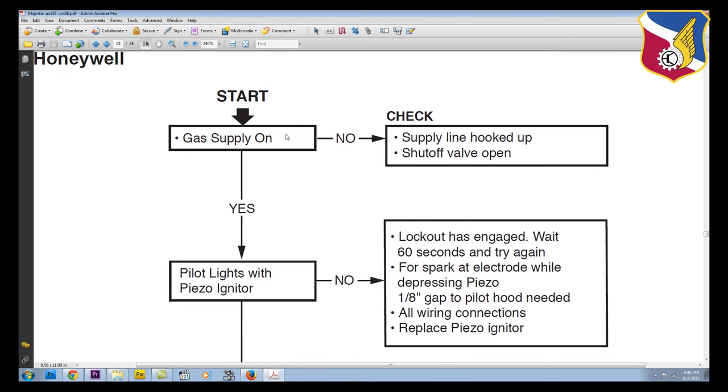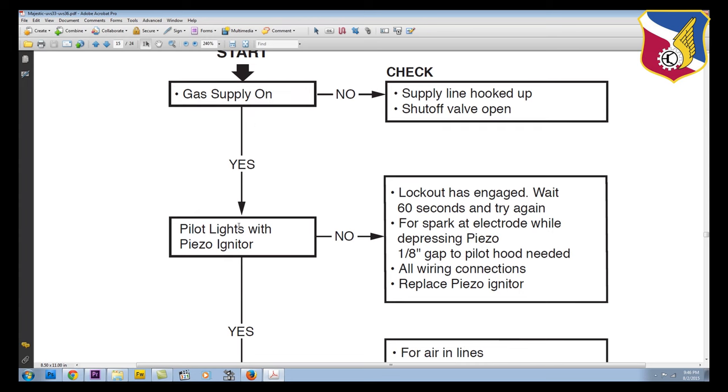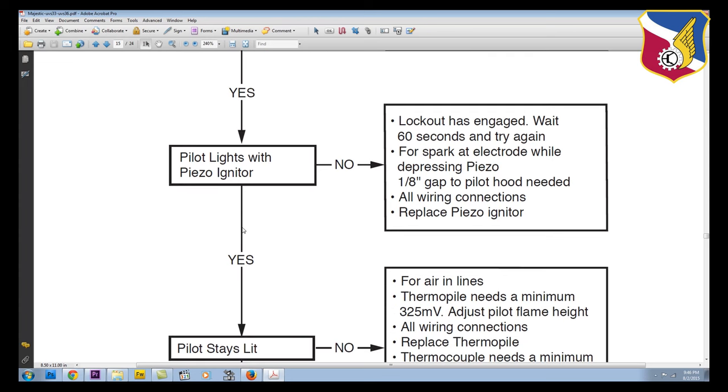So let's start out at the start of the flowchart. And as you go down the flowchart you can see the first question asks, does the gas, do you have gas coming to the unit? Now if you don't have gas it says check if you have it hooked up or if the shutoff valve is open.